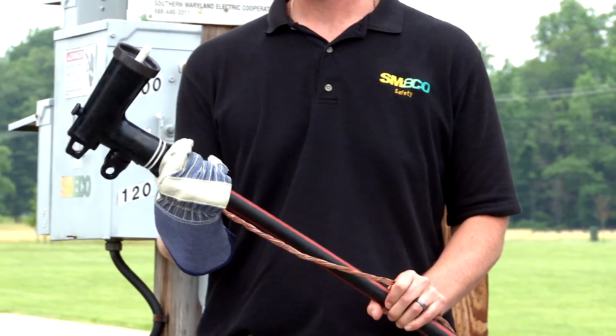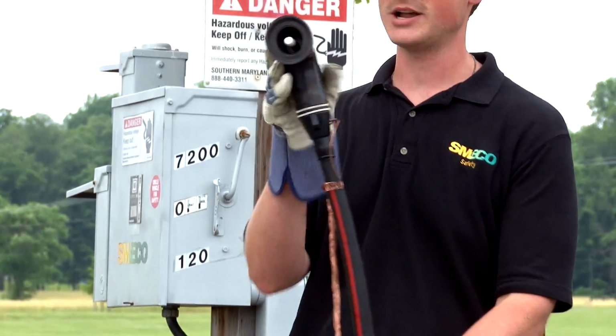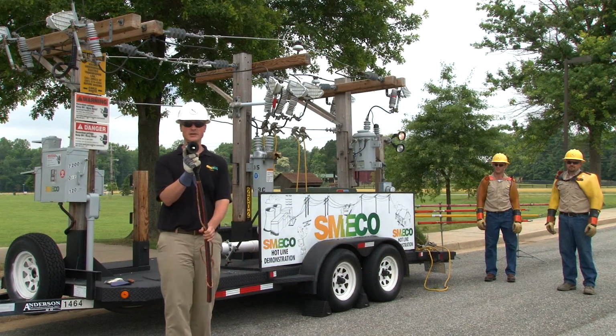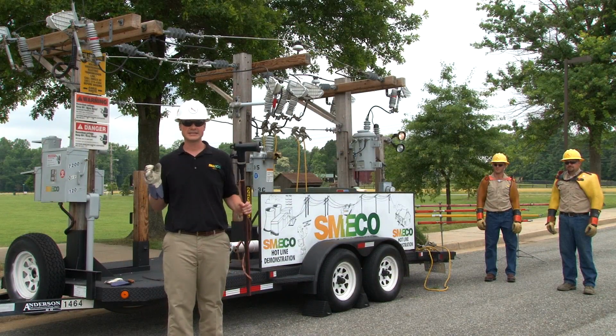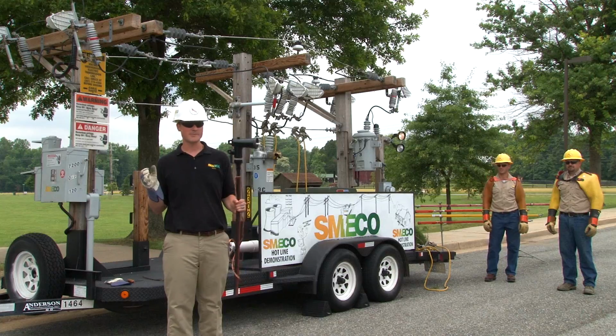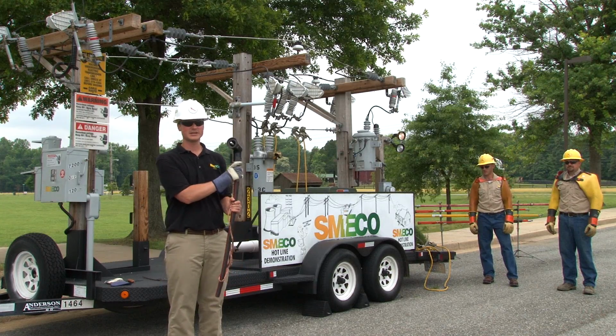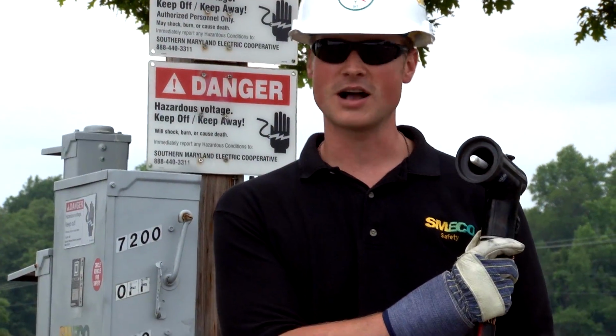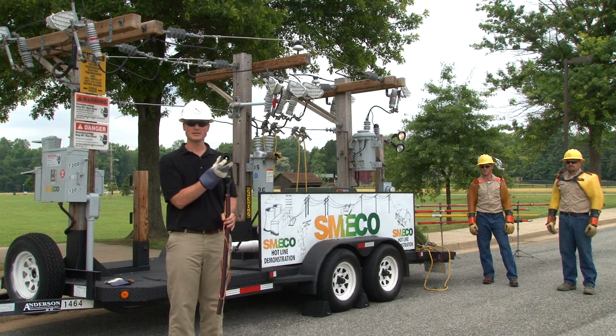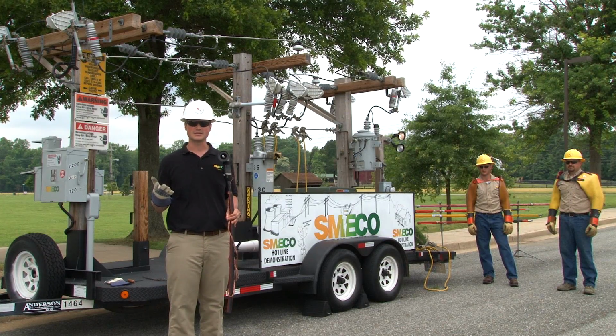These elbows can actually plug into the transformer. It comes through the ground and plugs into the transformer just like that. If there's significant trauma or an event to that pad mount transformer, it could potentially knock this elbow off its socket, and this center conductor here could remain energized.